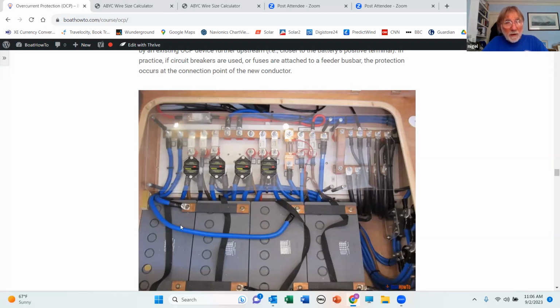And then we follow the conductors coming off the positive posts. We come to a big bus bar. So remember, we're allowed up to 72 inches, as close as practicable, but not to exceed 72 inches coming off the batteries. We're starting to push it here. And we've got all of these fuses. So this looks great. Now, each one of these is now a main fuse, because each one of these is connected back to the battery. So each one of these needs a high AIC rating. It's not like we put a single fuse in here, like a Class T fuse. Every one of these has to have a high AIC rating, and then each one of these is sized with a maximum amp rating based on the size of the conductor coming off it. We've also got some circuit breakers here. I don't know why they've got redundant circuit breakers.